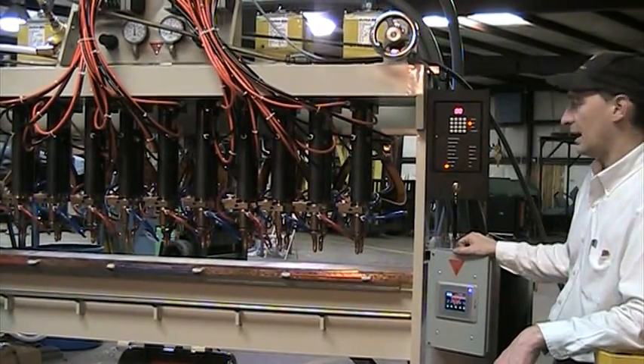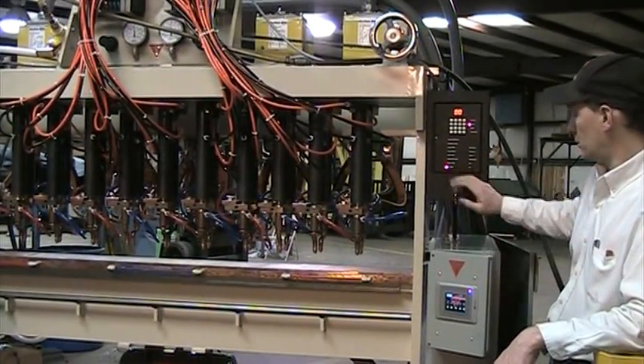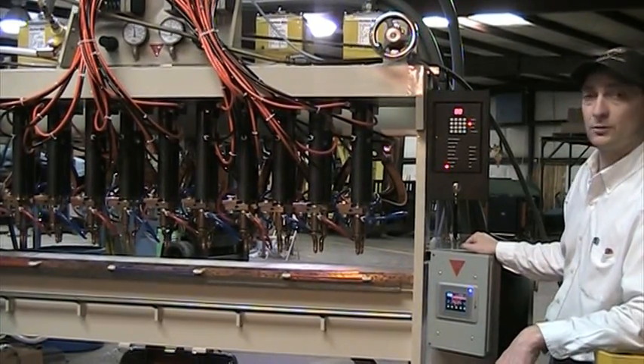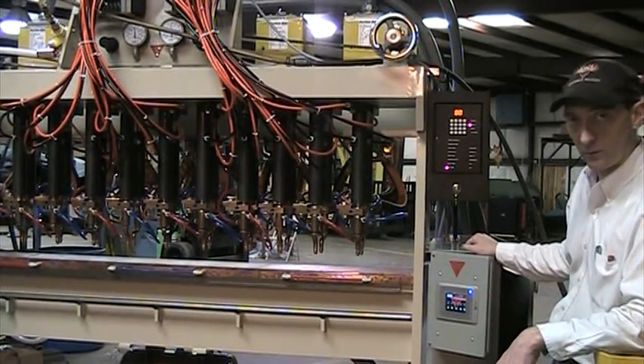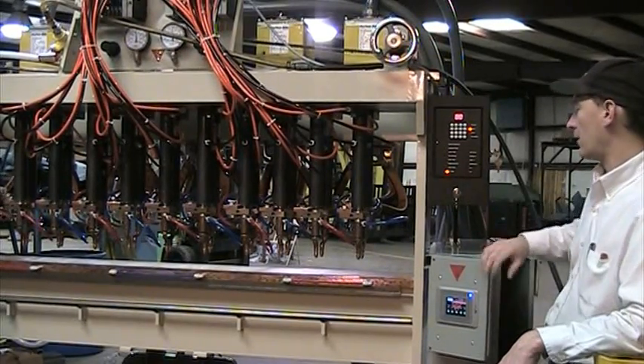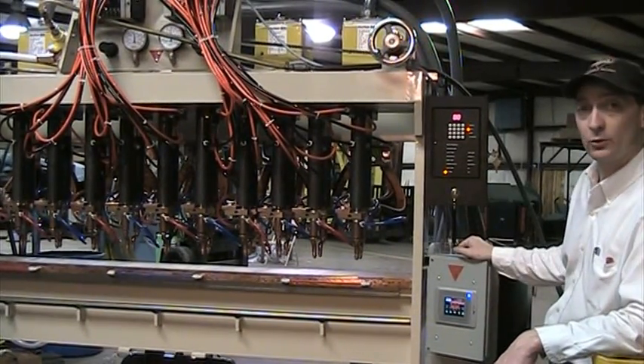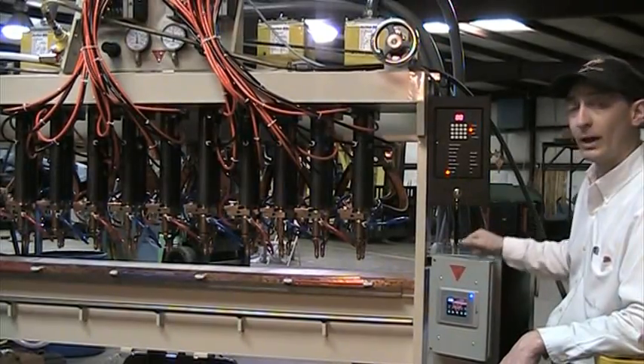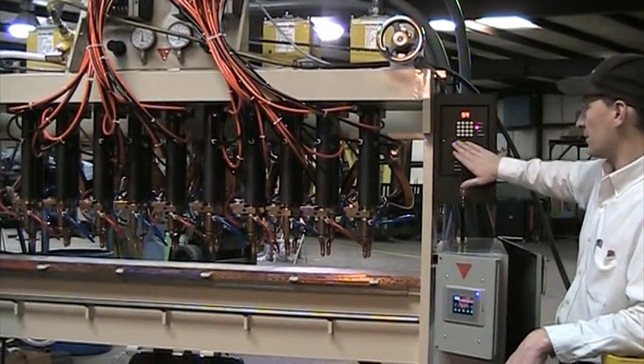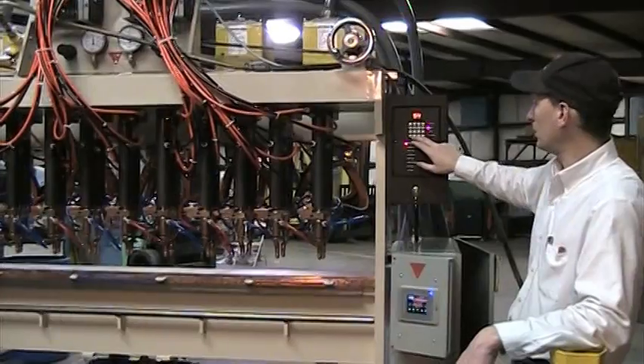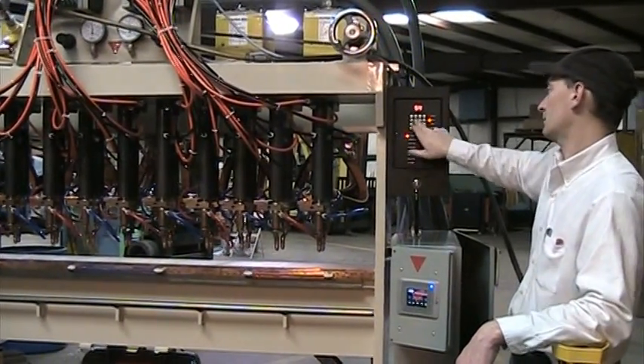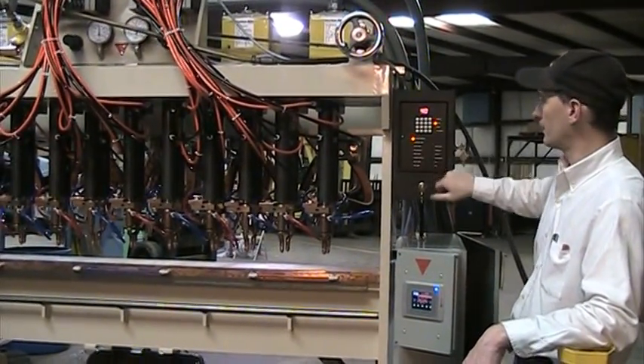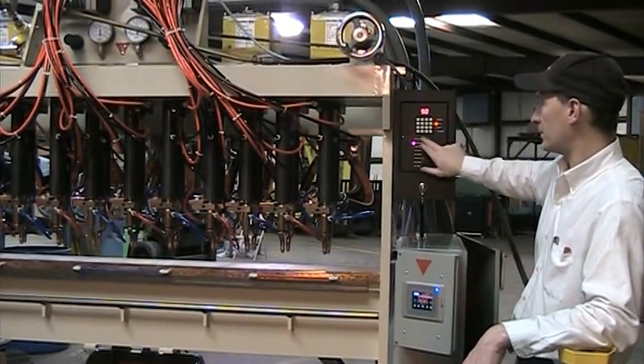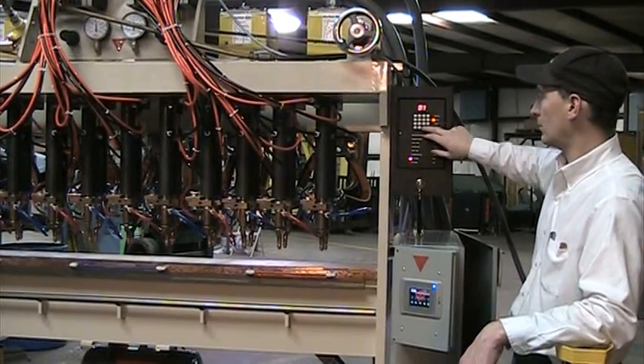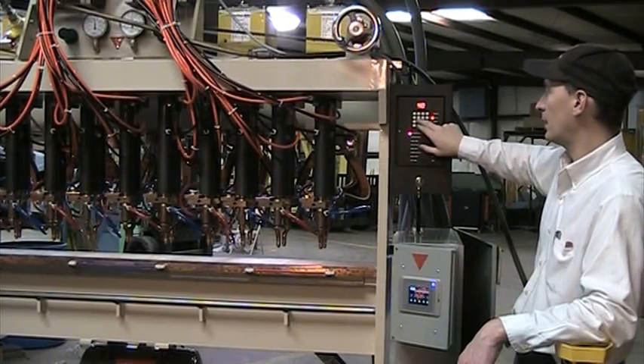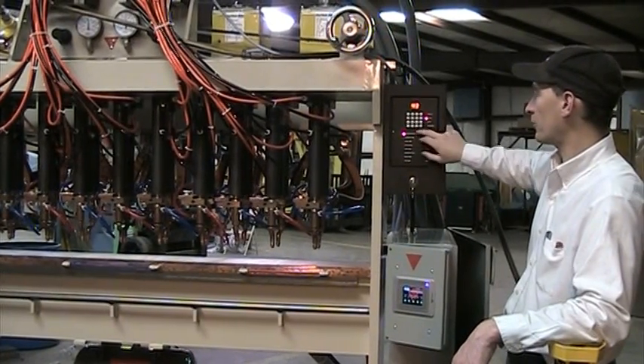And finally, an off time of 0. This is what denotes to the PLC itself that you finished all the steps in the control. So when it gets to this point, it's counted that it's welded 5 times, it sees that there is no signal left, and it shuts off and goes back to the beginning. This is the pattern that you'll use no matter what programs you build. If we go to program, say, 40, we've got the same scenario. 50 on the squeeze time, we've got our weld program, 1 on the hold, 2 on the off, and we go from 40 to 43.